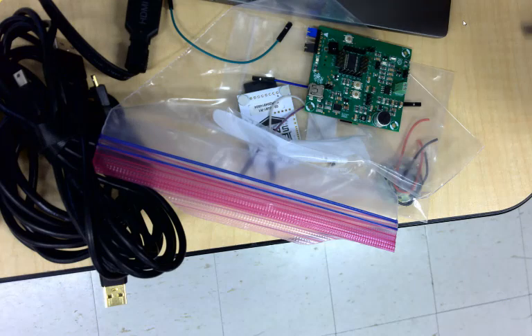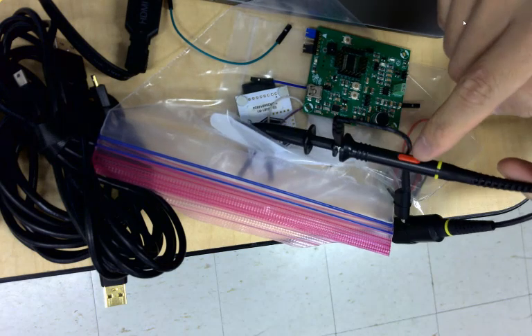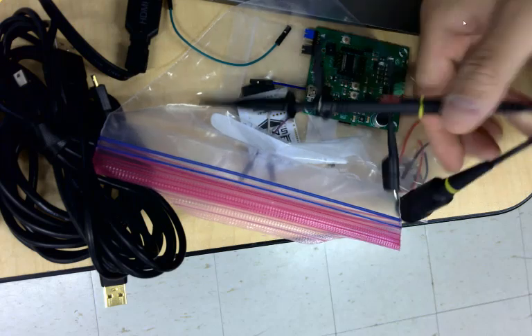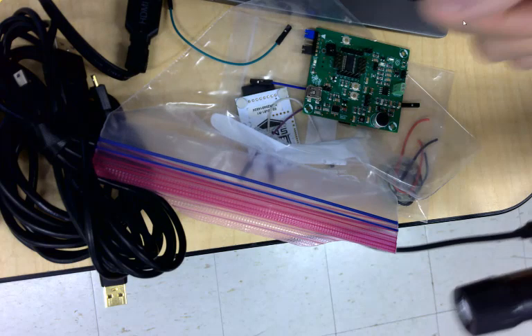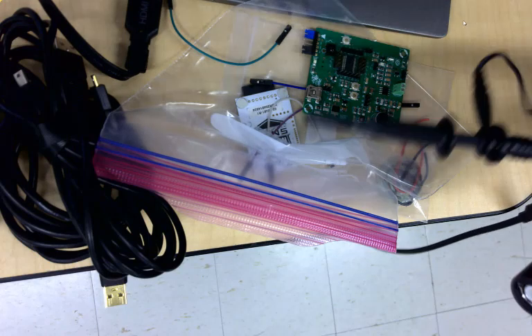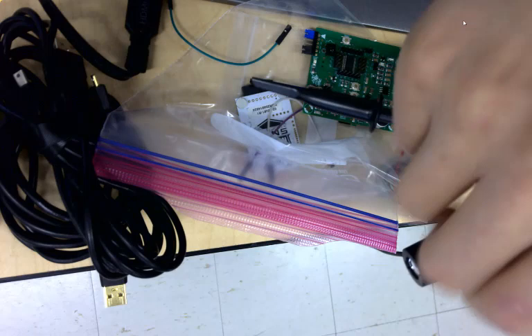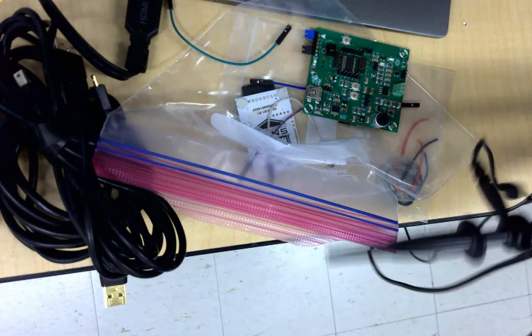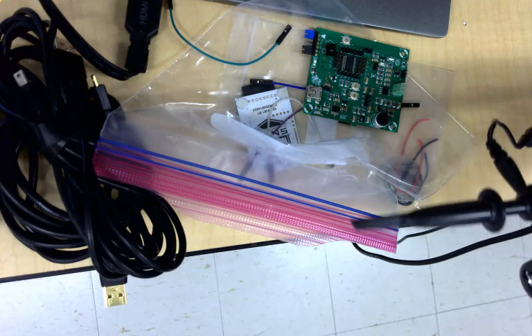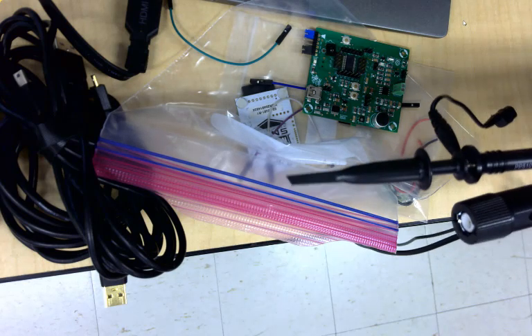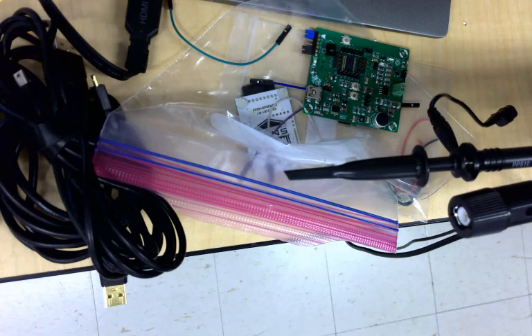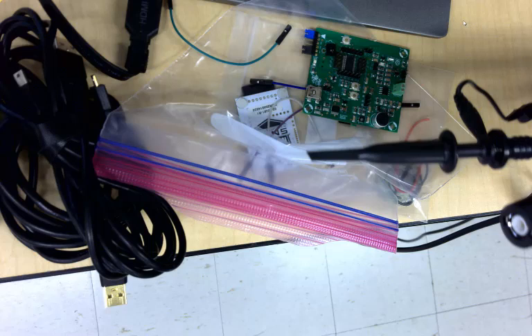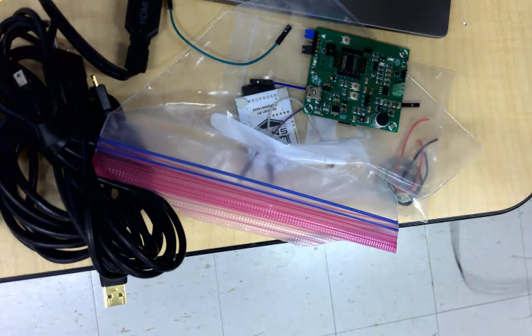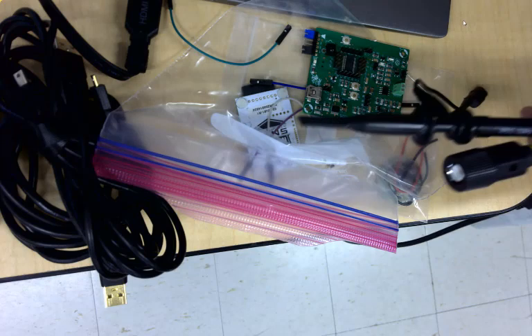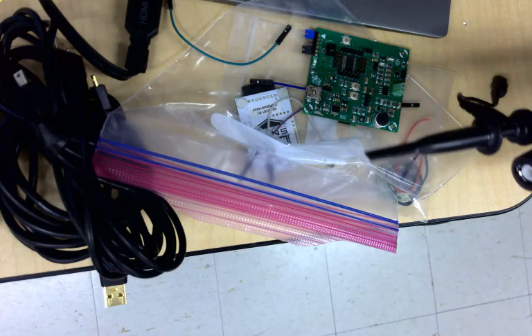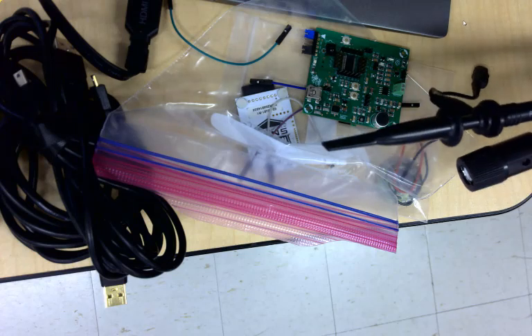So 3 steps. First step, check here. Which X do you want to use? 10x. Okay. Second step, calibration. You don't have to do it every time, because I don't believe people are coming here every week to mess with the screw. If you calibrate once for the rest of the semester, most likely you are getting a good probe. You don't have to do it every time. However, it should be the second step you do today. I have to figure out where the standard signal is on your oscilloscope over here. It should have one, okay? And the third step is check the probe's setting, see if it's a 10:1 ratio.